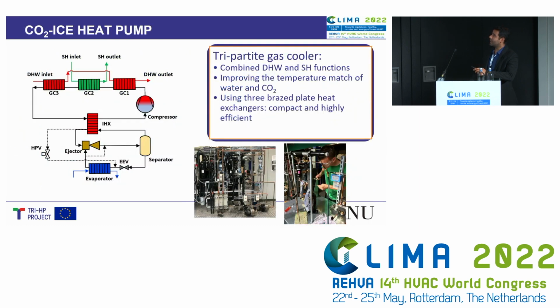All right, so the first prototype is the CO2 heat pump system. Here we have the schematic of the heat pump. We use the tripartite gas cooler because we were able to combine the domestic hot water and space heating functions together. We were able to improve the temperature match between the CO2 and water, which results in improved efficiency of the system. By using a brazed plate heat exchanger, we were able to make a compact and highly efficient system. We tested the heat exchangers at a university, and finally we built the unit in Switzerland.